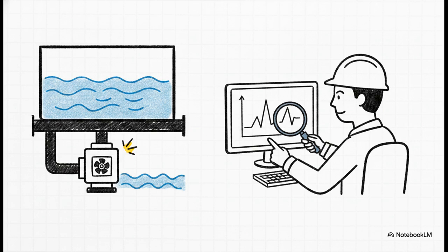If a pump starts drawing too much power or a reservoir is filling way too slowly, they don't have to guess what's wrong. Without logging, they could be facing a catastrophic citywide pressure drop before anyone even notices. But with SCADA, they simply query the historian, cross-reference motor hours with flow rates, spot the degrading component, and schedule maintenance long before disaster strikes.